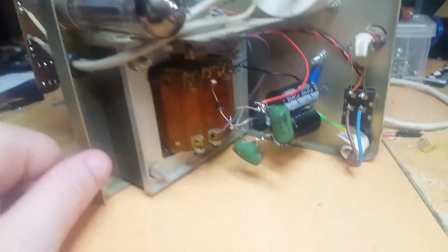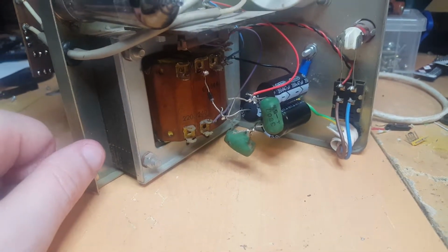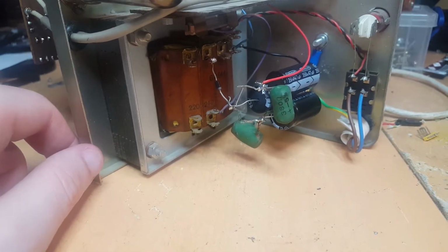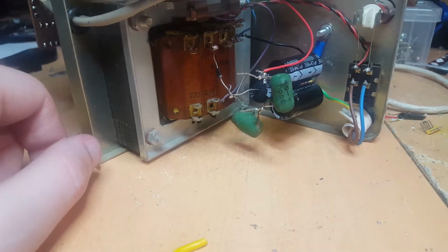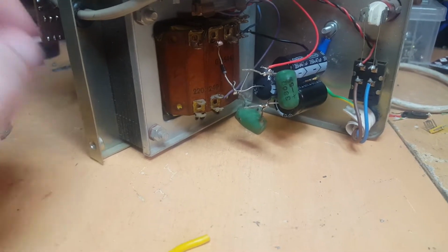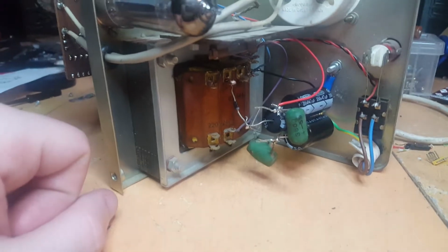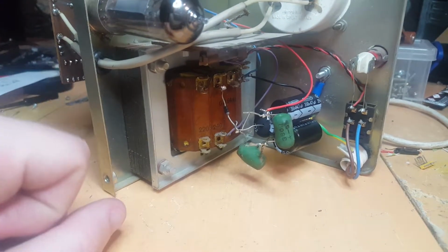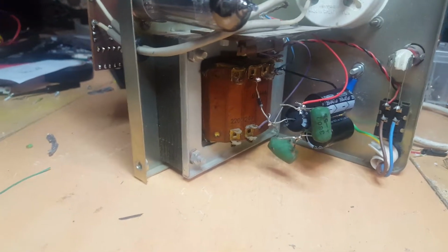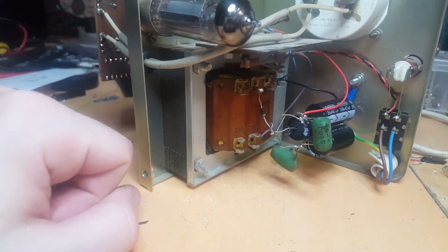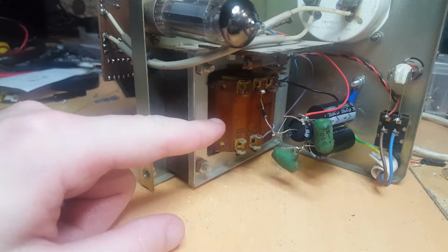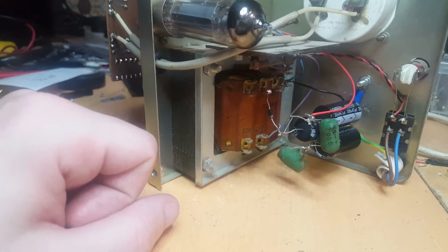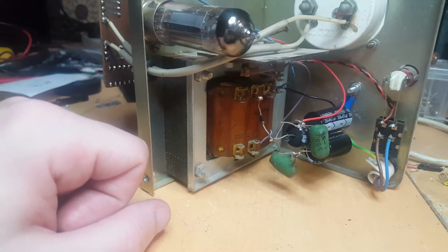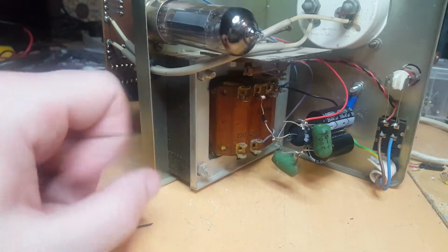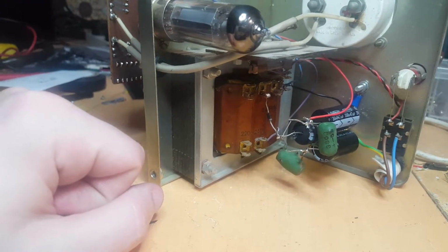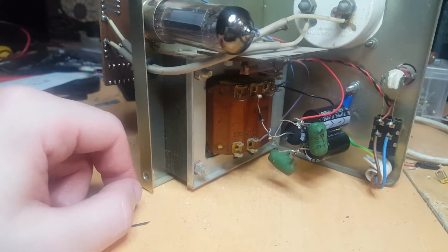The case is connected to ground. It is also connected to the transformer secondary. So all of the electronic switching stuff is connected to earth ground, which is good. It's good for EMI, I suppose, and these days it's a nice safety thing because it means that a primary to secondary fault in the transformer is just going to trip the RCD plug I'm putting on the end. So even if the insulation in the transformer fails, and it is 50 years old, no one dies. Again, caveat I'll get to.